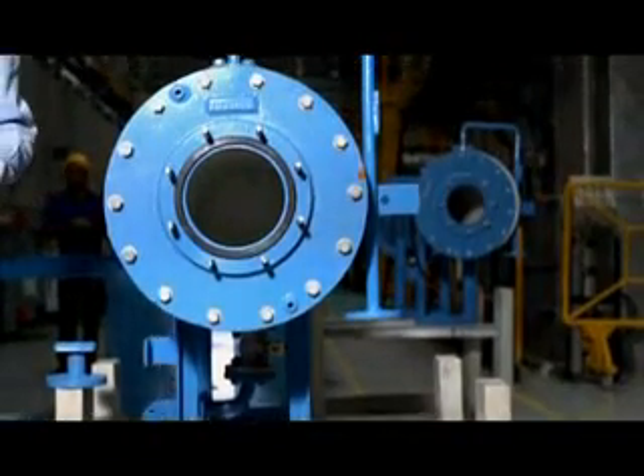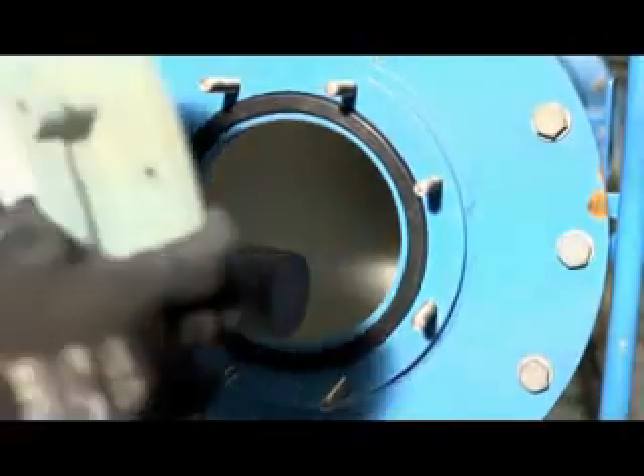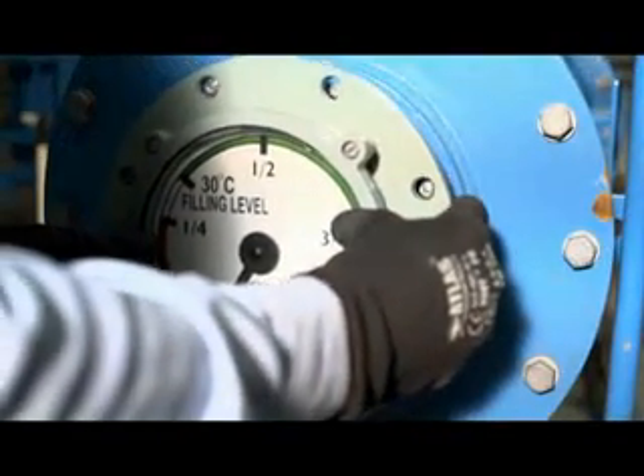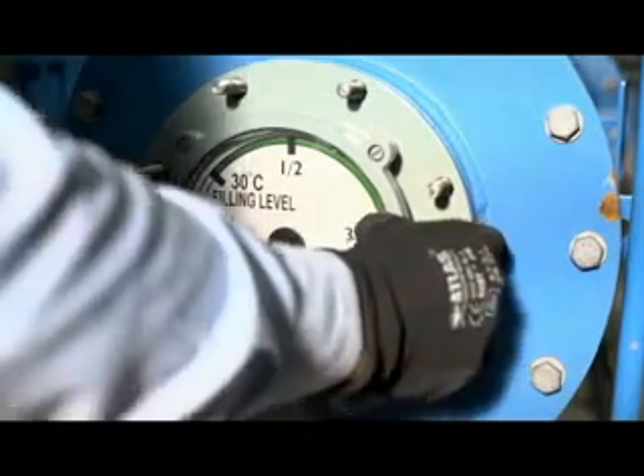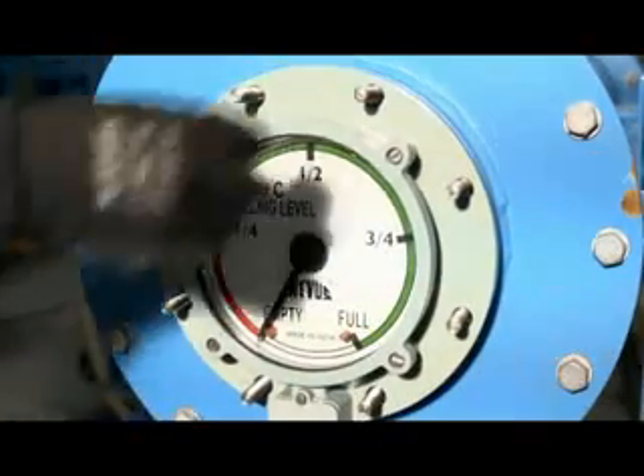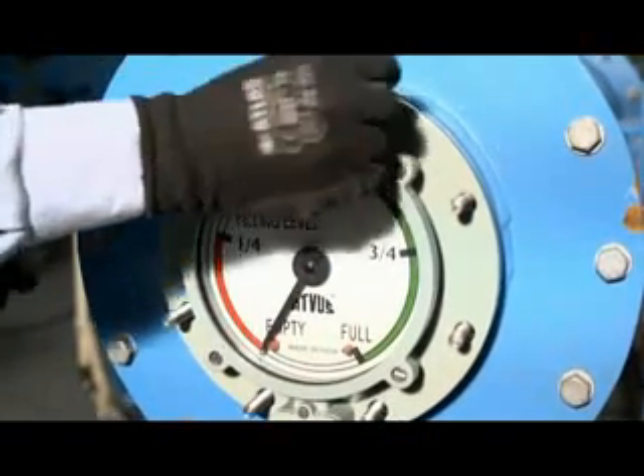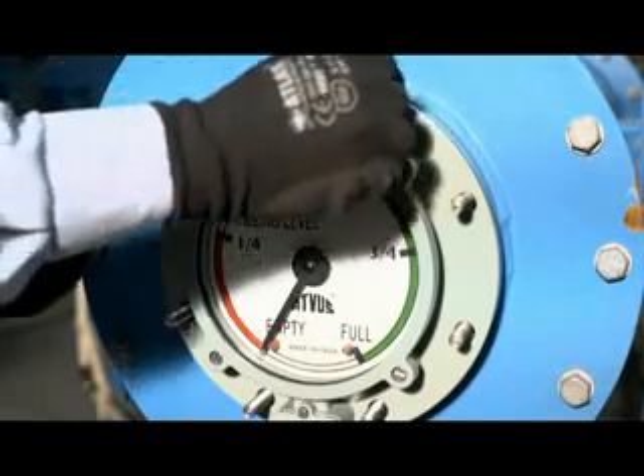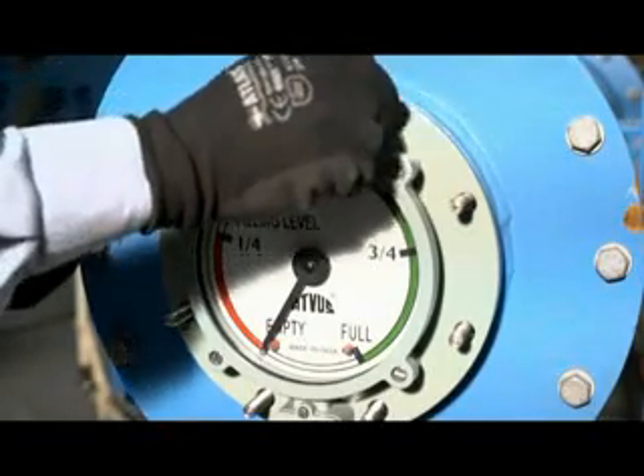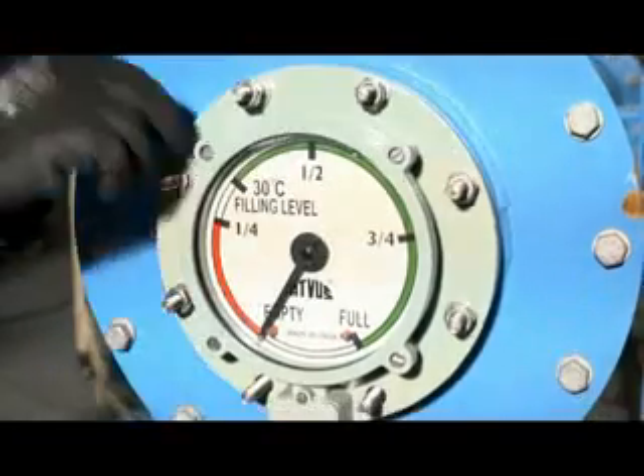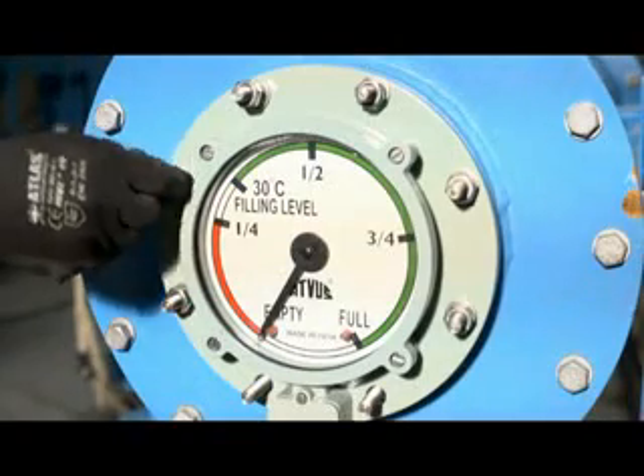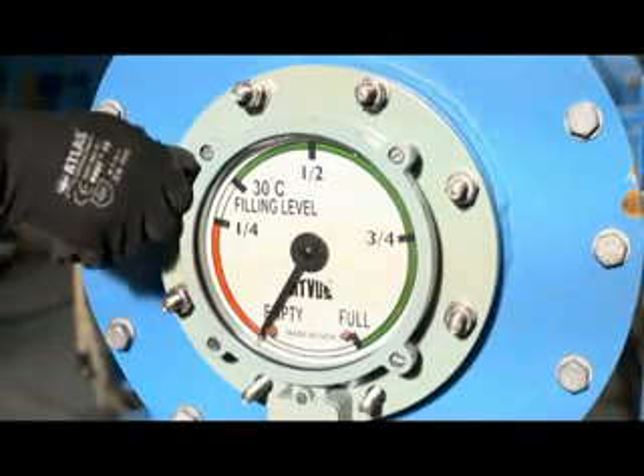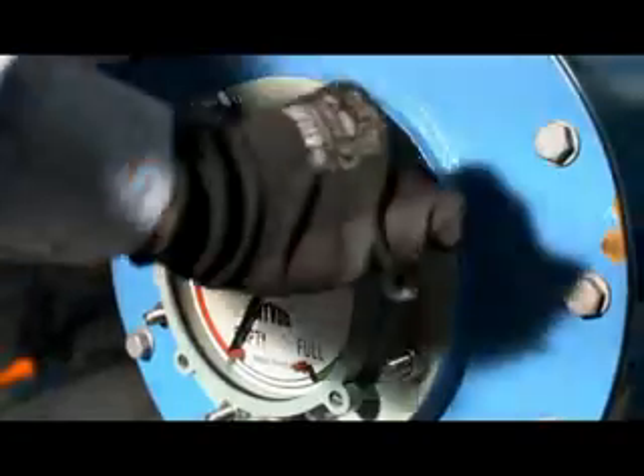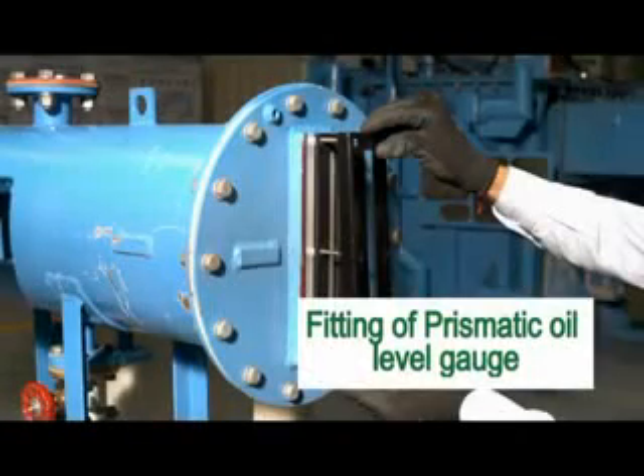Mounting of MOLG is being done through suitable size of oil seal, gasket, hardware, and tightening is done as per prescribed torque. It has 1 or 2 sets of contacts for alarm or trip circuit. Prismatic oil level gauge indicates oil level in tank or conservator. Window opening is fitted with grooved Perspex sheet and metal frame to give clear indication of oil level. This gives a clear visible indication of the oil level in the conservator.